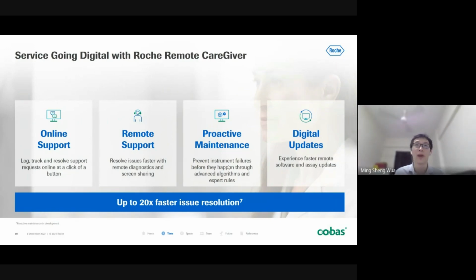This is where we are able to gather the data from your instruments and monitor it in the background. There is an algorithm that is able to detect whether an instrument is in a good condition or a bad condition. If it's in a bad condition, it prompts us to go and do proactive maintenance before the analyzer has any issue. Finally, digital updates update all your package inserts, MSDS, or value sheets automatically.